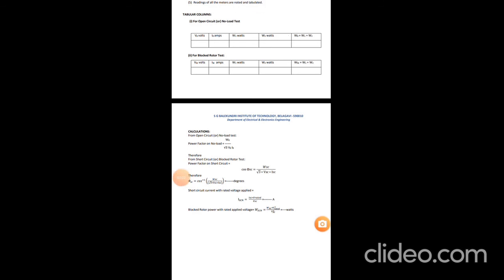Readings should be taken for the no load test, as I explained in the procedure. We note down the voltmeter, ammeter and wattmeter readings, which are the no load voltage, no load current and no load power, in tabular column 1. These are the readings of the no load test, or open circuit test, on the three-phase induction motor.